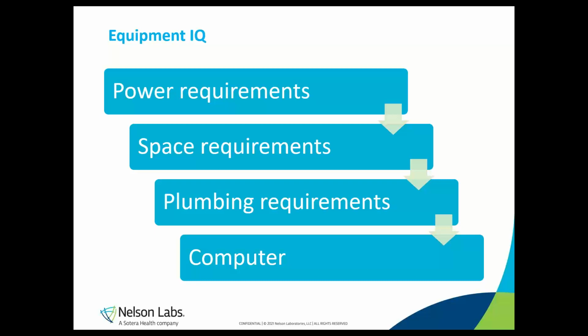Does the sealer connect to a computer? Is there special software to control the sealer that needs to be included in the validation or maybe validated separately? The protocol should contain a list of what needs to be checked, and then those items are verified and documented during the IQ. Your IQ needs to be performed initially and whenever the sealer is moved or the utility connections are altered.